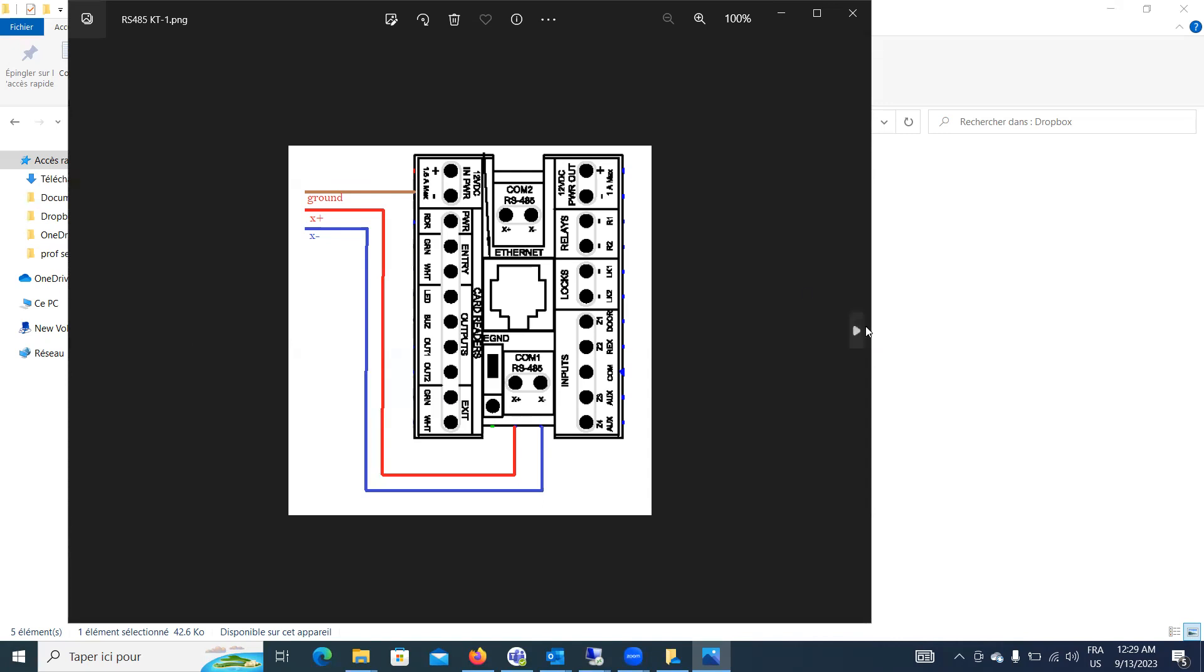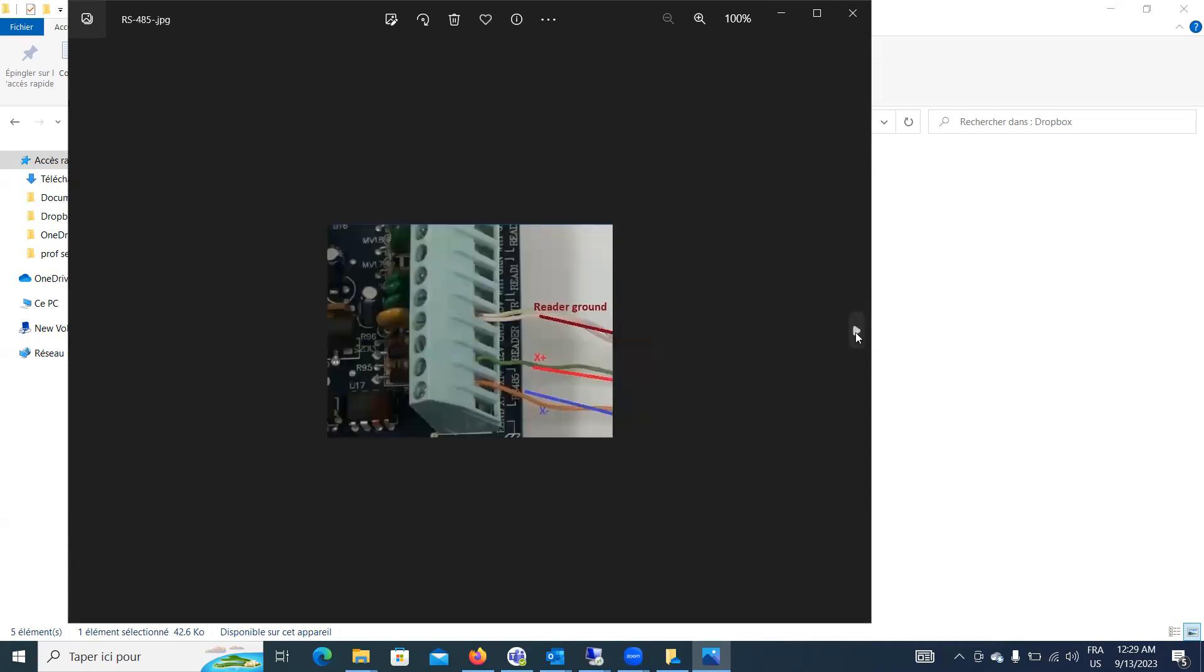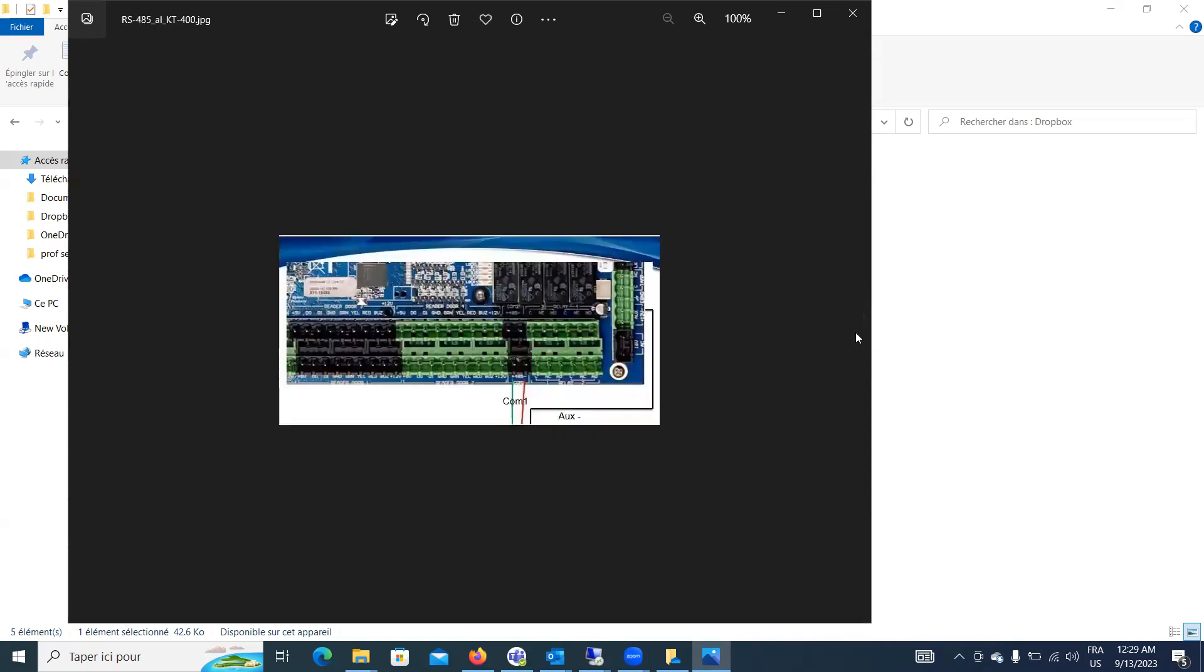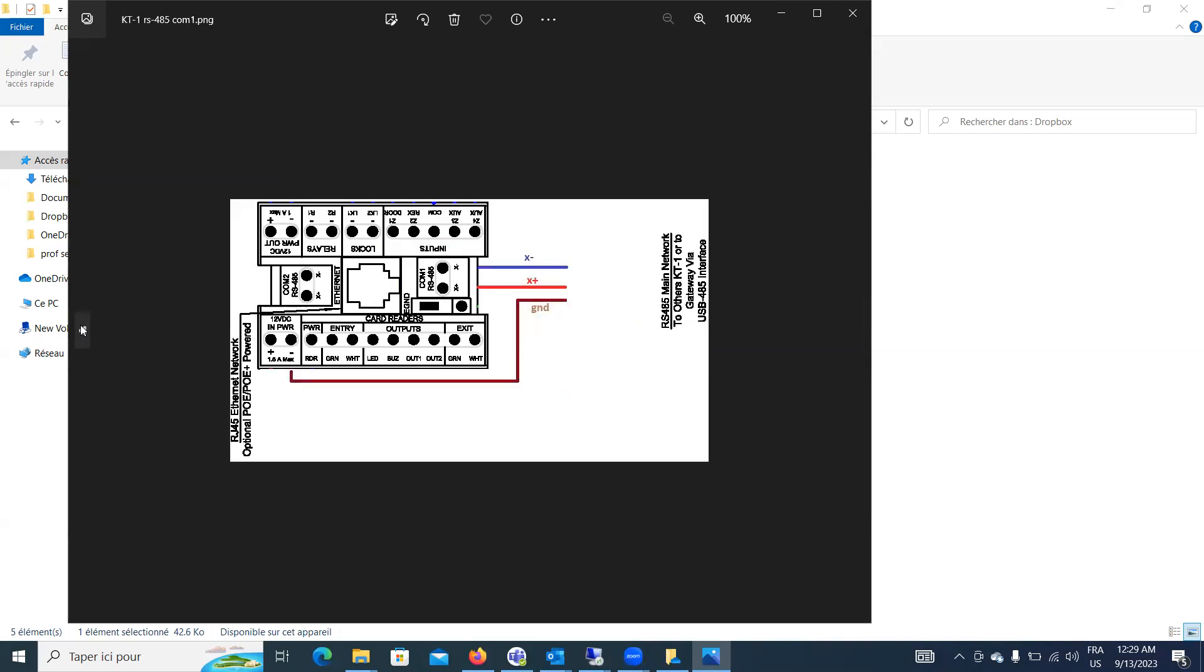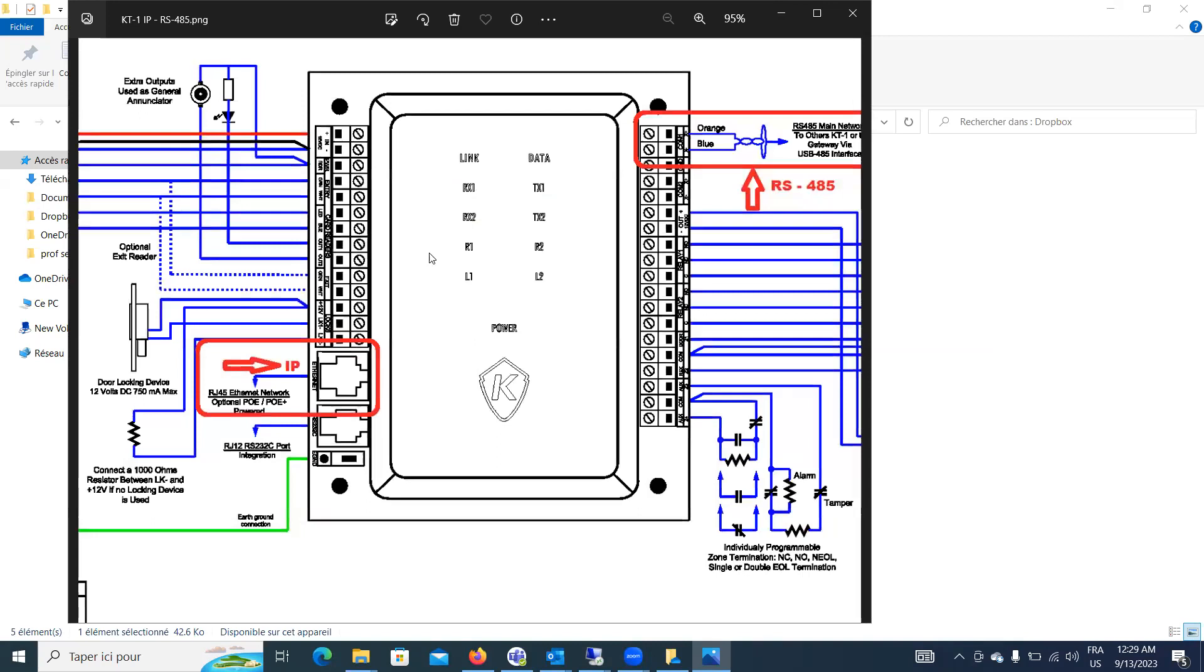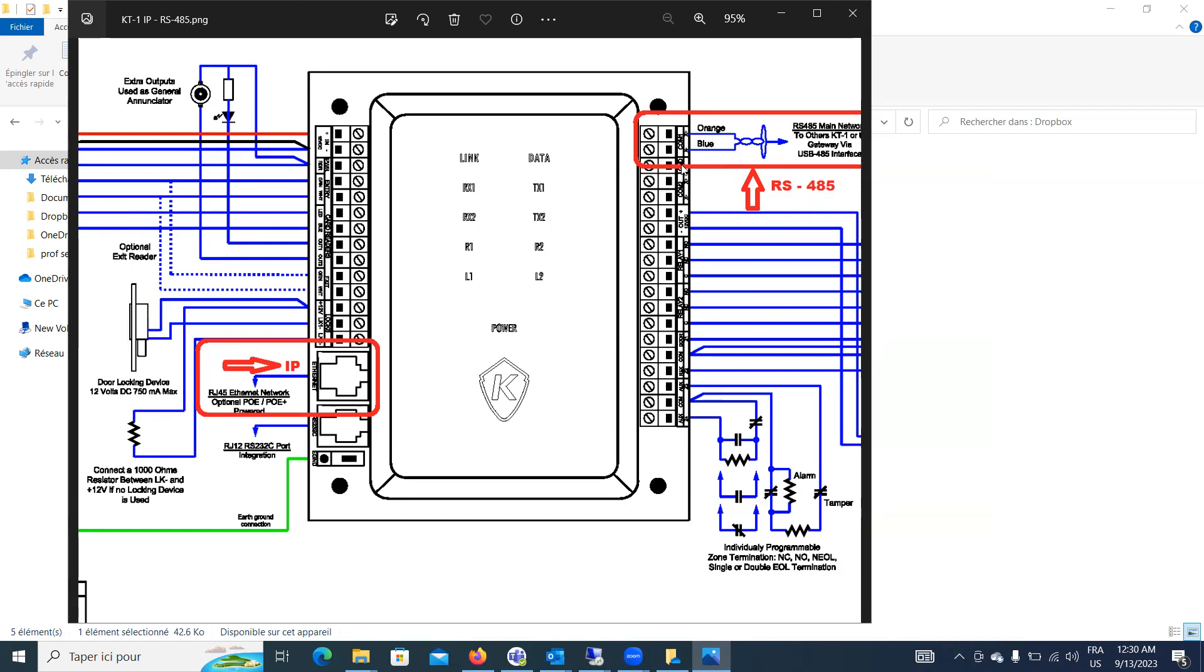And we can see, for example, the KT1. These KT1, which come with the PCB additional board, you have the X plus, X minus, but you also have the ground. So just to make sure you don't have any communication issue, even if you have everything in DC or afterward, you should go with three cables, X plus, X minus, and the ground.